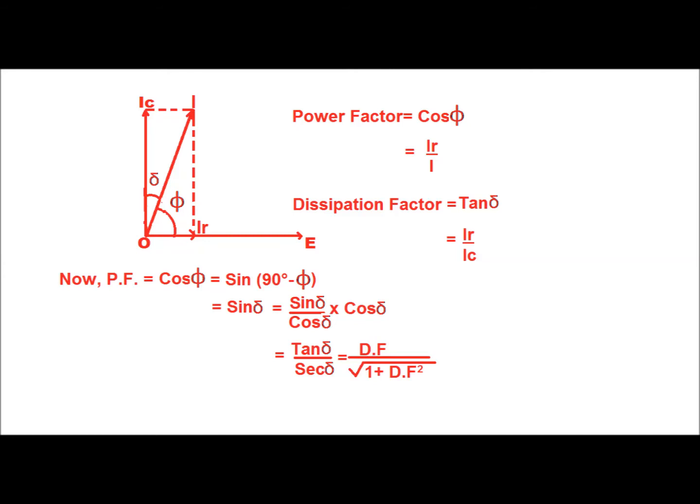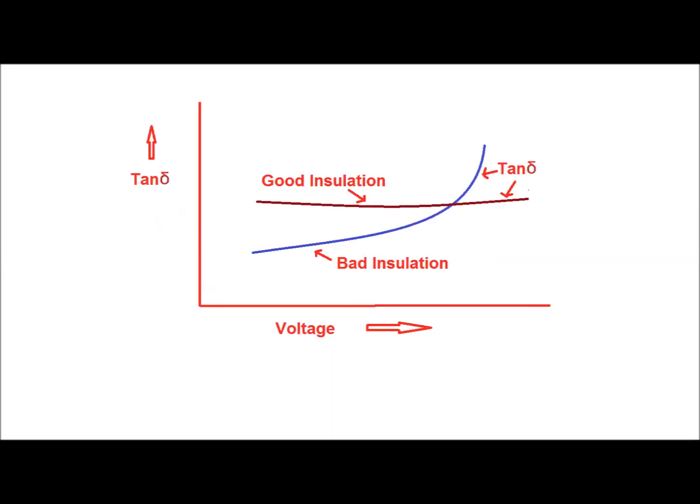That is the ratio of the resistive component of current to the resultant current. Dissipation factor tan delta equals the ratio of the resistive component of current to the capacitive component of current. The more the resistive component of current, the more the tan delta value. If you solve the equation, the power factor equals the dissipation factor divided by the square root of one plus dissipation factor squared. This is the relation between power factor and dissipation factor.